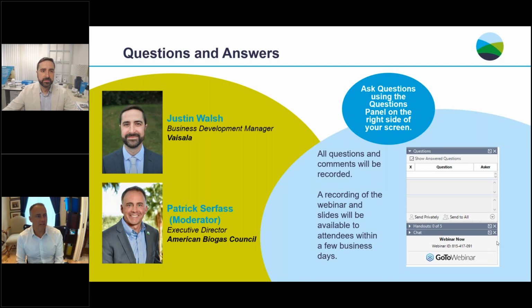Okay, great. And actually, this one relates to that as well. So regarding maintenance of your products, does Vaisala offer that kind of service, service in the field, commissioning to get things going, or calibration of your instruments? So we don't offer field service, as these are pretty straightforward. You wire them up, you install them, they come calibrated, they're ready to go. Make sure you set whatever pressure compensation you want to use, and into the pipe it goes. We have free tech support. Field calibration is detailed in the manual, but you can send it to us for calibration. We do have in-house calibration if you wanted a traceable calibration certificate for that. But yeah, they're so simple, it doesn't really warrant field service people.